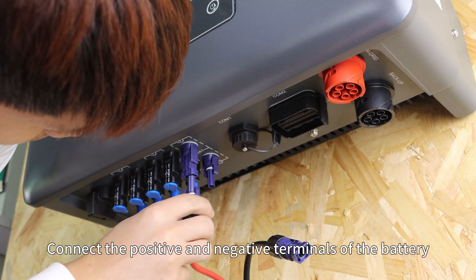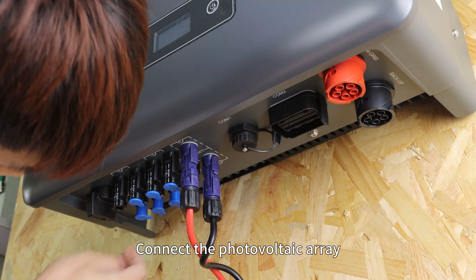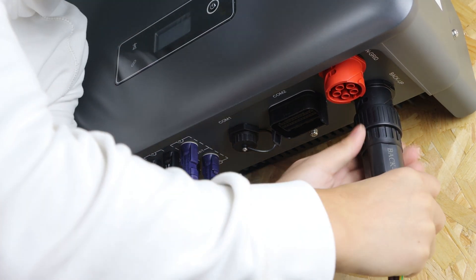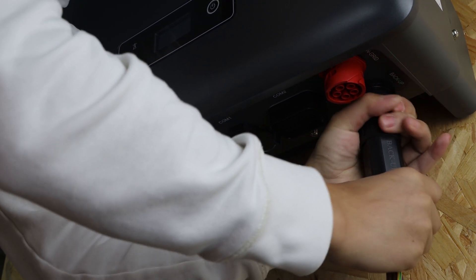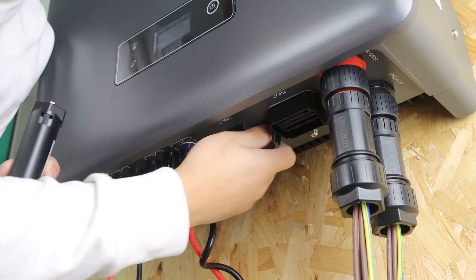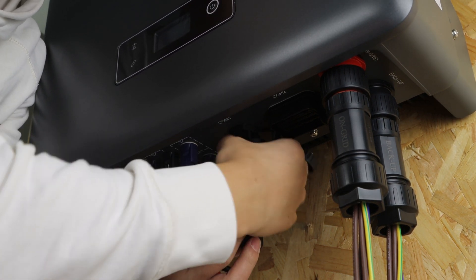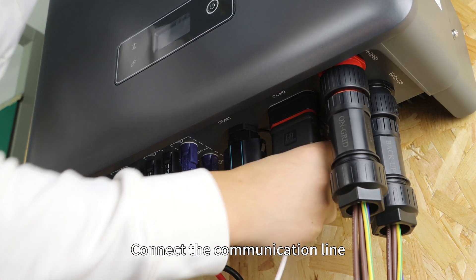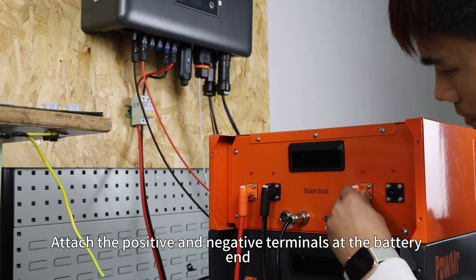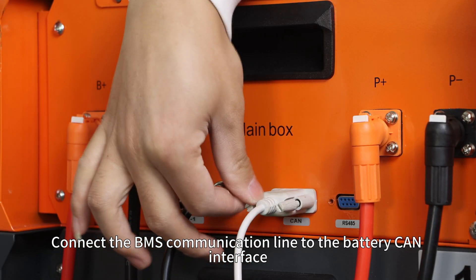Connect the positive and negative terminals of the battery, then connect the battery and the photovoltaic array. Connect the AC terminal and the remote monitoring module. Connect the communication line. Attach the positive and negative terminals at the battery end, and connect the BMS communication line to the battery's CAN interface.